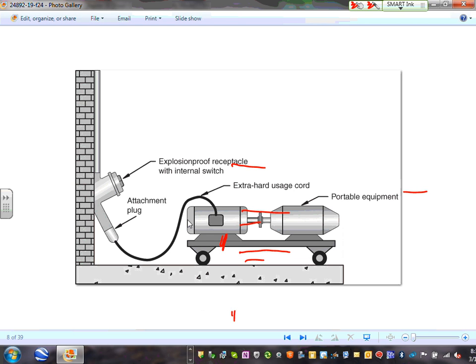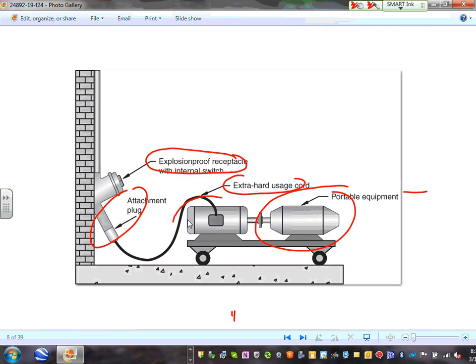hazardous location. If you are to put equipment, guys, in a hazardous location, look what happened. The switch, this is explosion-proof receptacle. 10 times more expensive than the receptacle that you can have here. And the equipment, guys, extra hard usage cord when you plug it in. This equipment also here have to be explosion-proof, so it can handle an explosion. You don't want anything to have arc and spark and ignite the area.